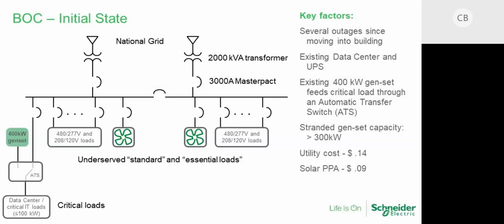So in addition to the data center loads, you can see there are other essential loads in the building that are fed solely by the utility grid. And whenever we lost utility power, all of those other essential loads and other standard areas in the building would go down, and just the data center environment would be backed up. That impacted our personnel. They couldn't conduct business when the building was down and there was a loss of power. They lost power to their workstations. They lost power to the air conditioning. So it was very interruptive to the business. If you go to the next slide.